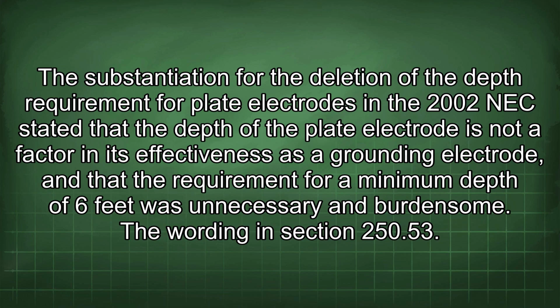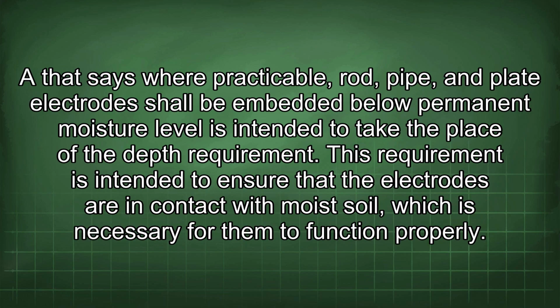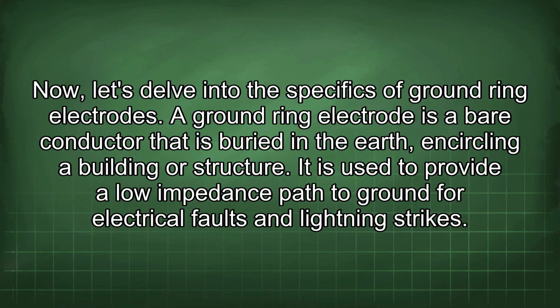The wording in section 250.53 that says where practicable rod, pipe, and plate electrodes shall be embedded below permanent moisture level is intended to take the place of the depth requirement. This requirement is intended to ensure that the electrodes are in contact with moist soil, which is necessary for them to function properly. Now let's delve into the specifics of ground ring electrodes.